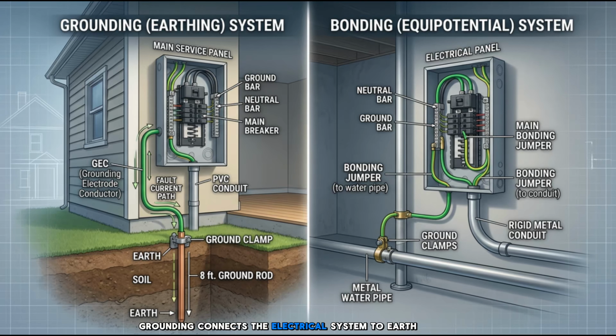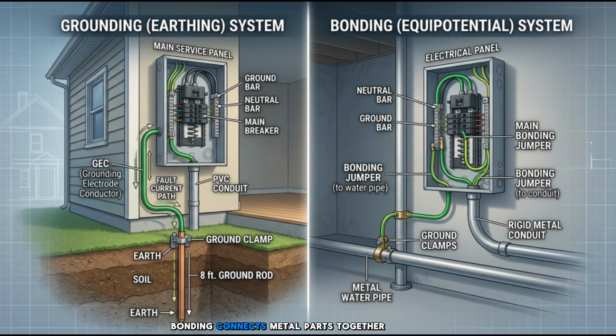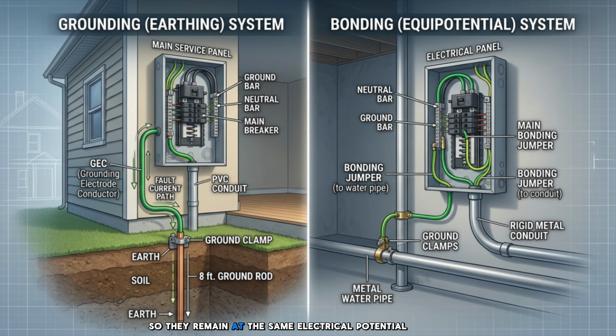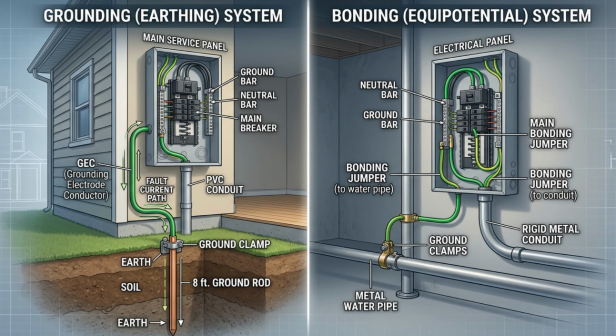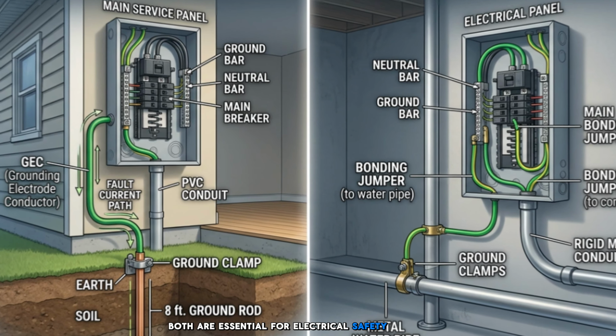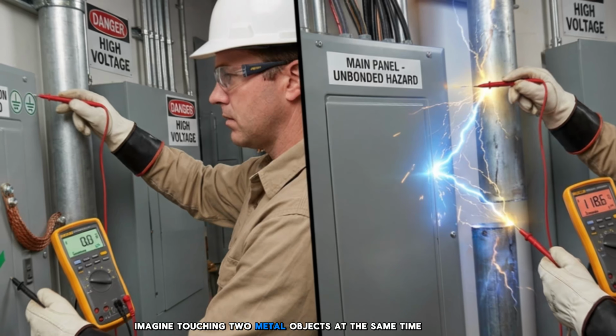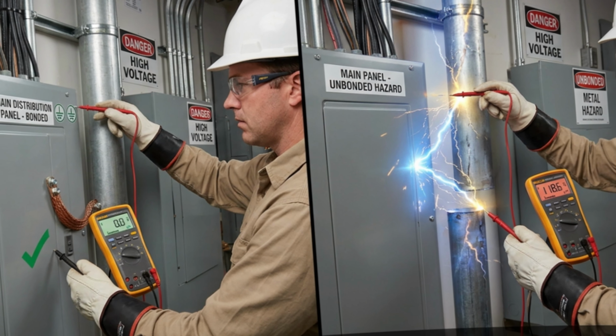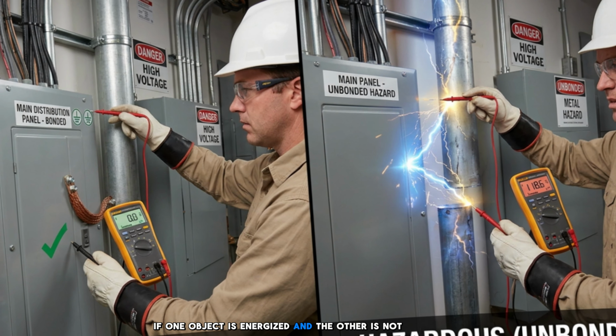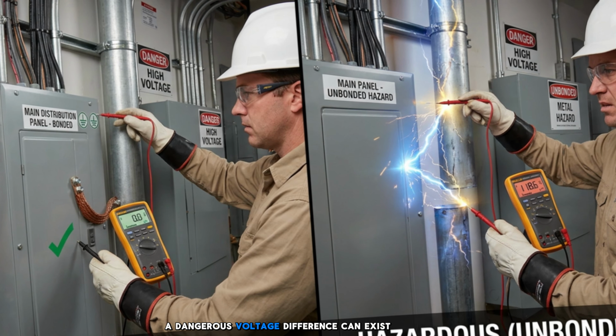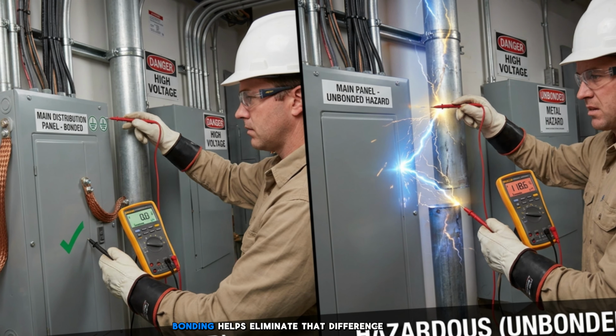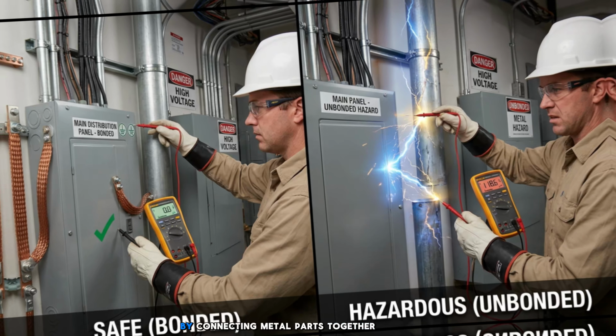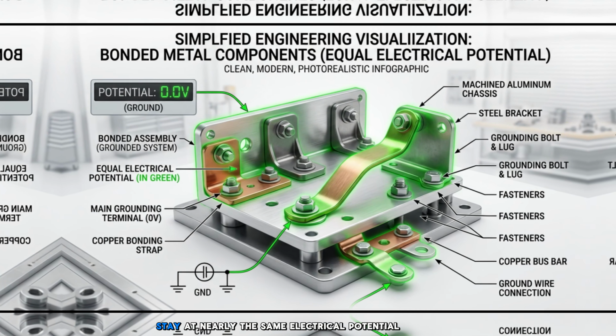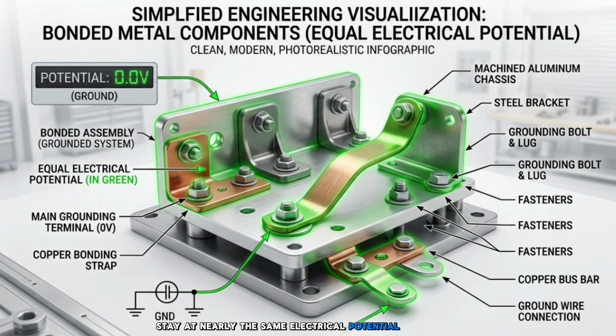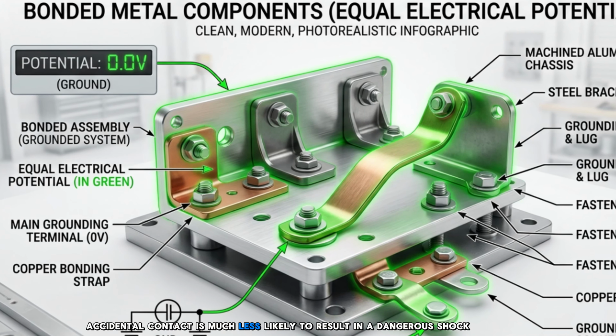Grounding connects the electrical system to earth. Bonding connects metal parts together so they remain at the same electrical potential. Both are essential for electrical safety. Imagine touching two metal objects at the same time. If one object is energized and the other is not, a dangerous voltage difference can exist. Bonding helps eliminate that difference by connecting metal parts together. Because all bonded metal parts stay at nearly the same electrical potential, accidental contact is much less likely to result in a dangerous shock.